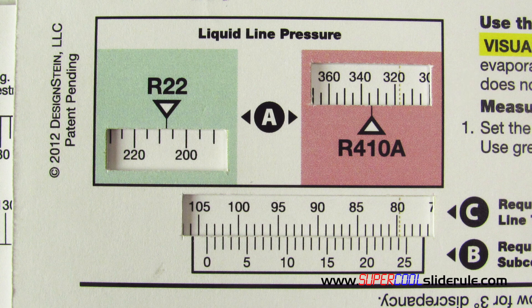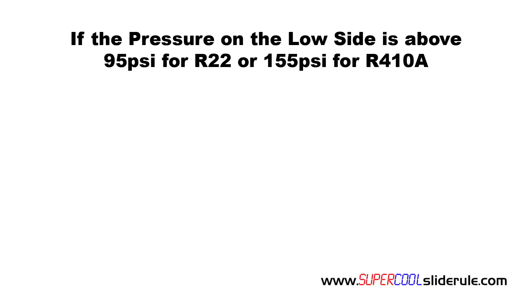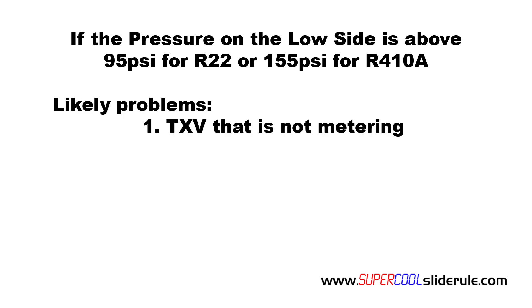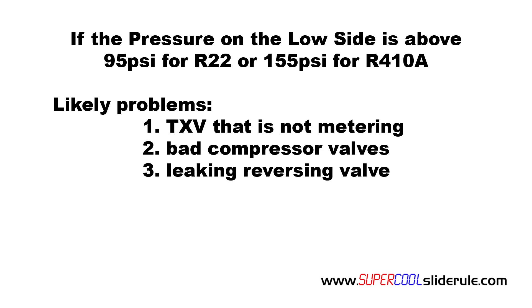This should be your discharge pressure of the unit. If the pressure is higher than this, the likely problems are a restriction at the metering device or an overcharged unit. If the pressure is lower than this, check the pressure on the low side, also referred to as the suction side of the compressor. If the pressure on the low side is above 95 psi for R22 or 155 psi for R410A, the likely causes are a TXV that is not metering, bad compressor valves, or a leaking reversing valve if so equipped.